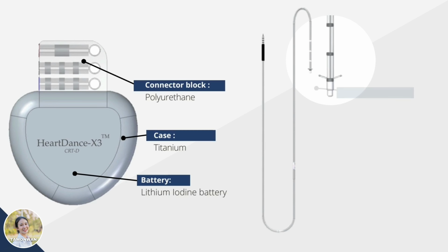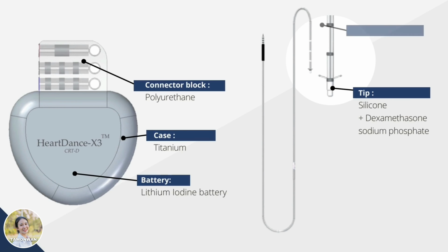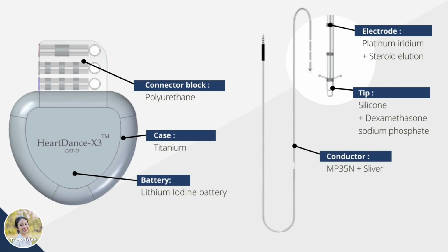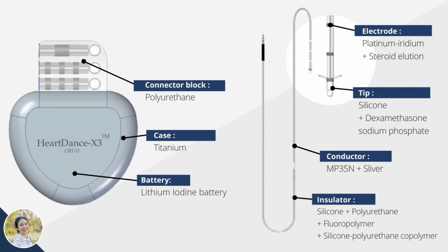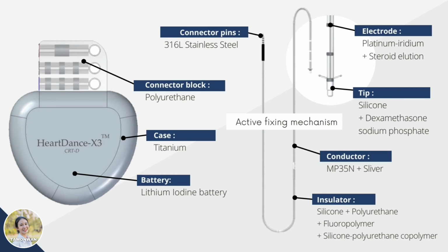If you zoom in, the tip of the electrode is made of silicone coating with dexamethasone sodium phosphate. The electrodes are made of platinum iridium coating with steroid elution. The conductors are made of MP35N, which is a nickel cobalt based alloy, together with silver. The insulators are made of silicone, polyurethane fluoropolymer, and silicone polyurethane copolymer, and each material is for each layer. And the connector pins are made of 316L stainless steel, so we use the active fixation mechanism for our device.